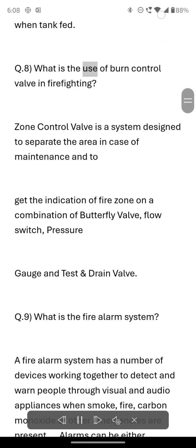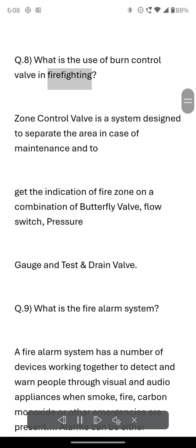Q.8. What is the use of a zone control valve in firefighting? A zone control valve is a system designed to separate the area in case of maintenance and to get the indication of the fire zone. It is a combination of a butterfly valve, flow switch, pressure gauge and test and drain valve.